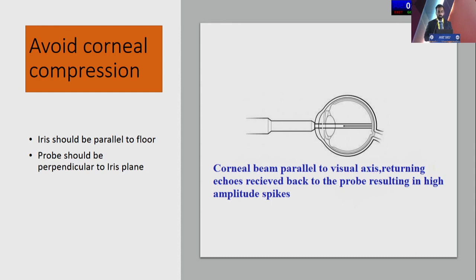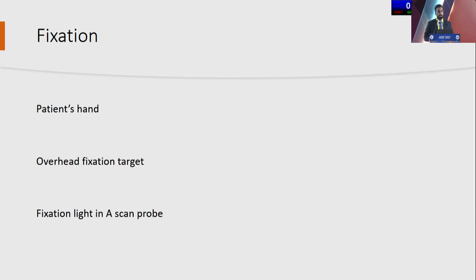When the corneal beam is parallel to the visual axis, the returning echoes received back to the probe will result in high amplitude spikes, which is what we like to see in a good A-scan measurement. So fixation can be helped by giving the patient a target to fix at. You can use the patient's hand, or you can use an overhead fixation target, or you can simply ask the patient to look at the fixation light in the A-scan probe.